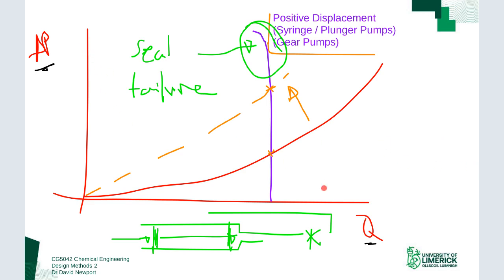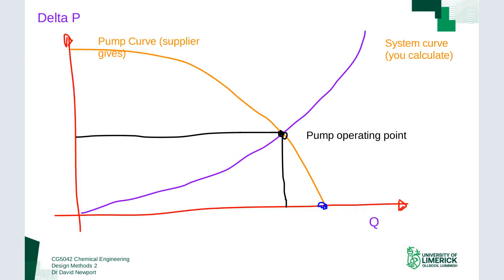Your objective is to produce the two curves: the system curve from your calculations, and the pump curve from the supplier, then look at the operating point. Based on that, look at where you want to be. For example, you may want to adjust the speed of your pump to reach a target point, or adjust your system to reduce the pressure so the pump moves into the region of maximum efficiency — and check that this gives your required flow rate.